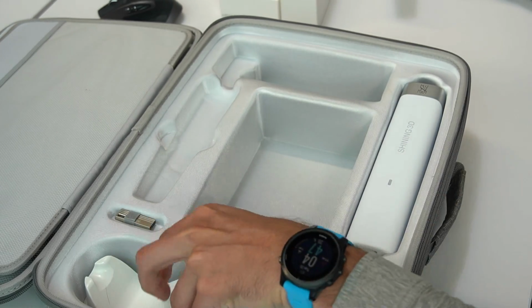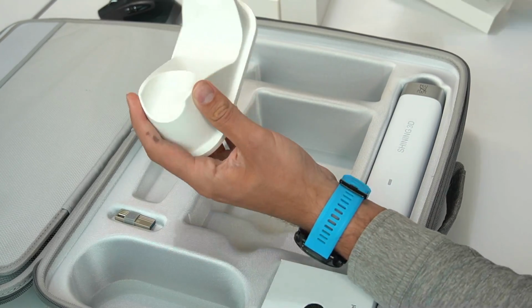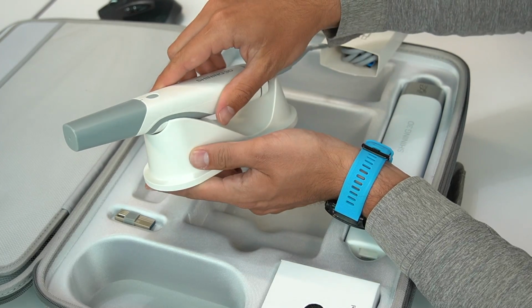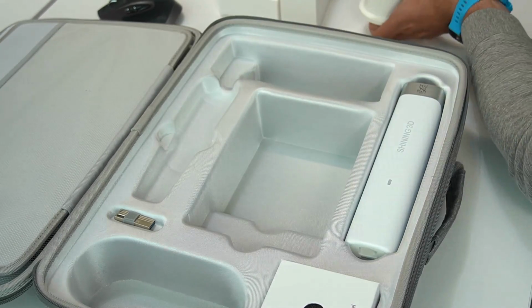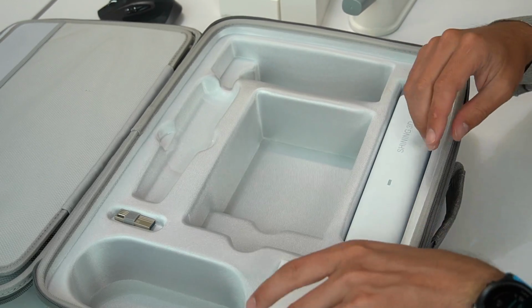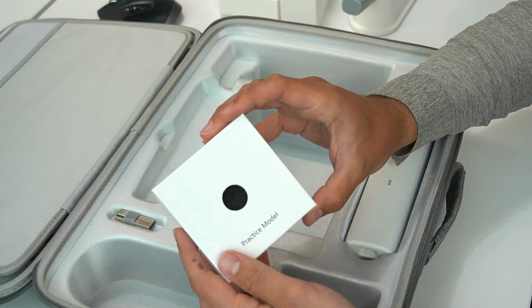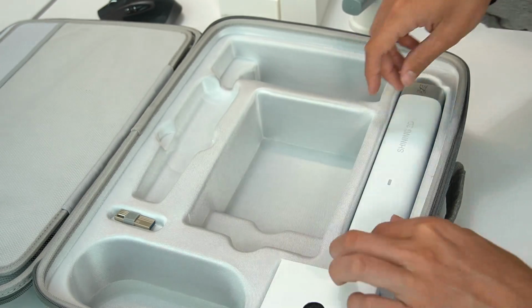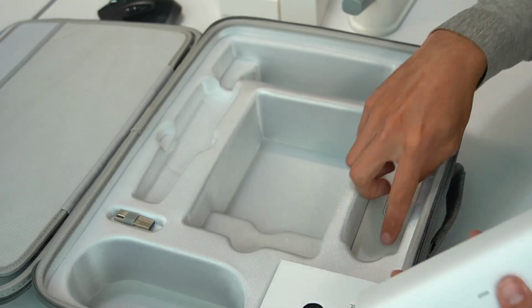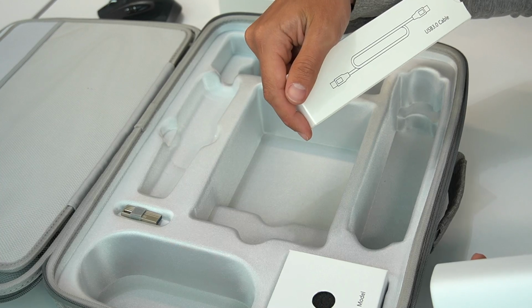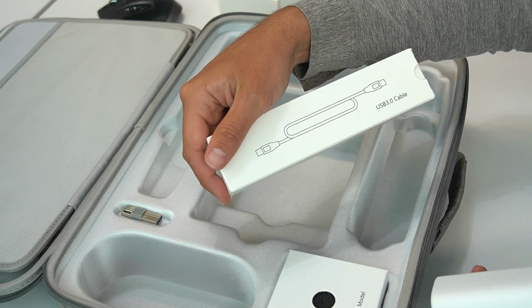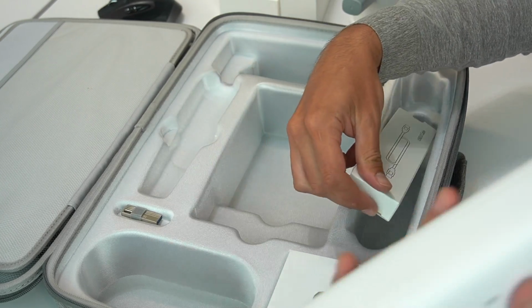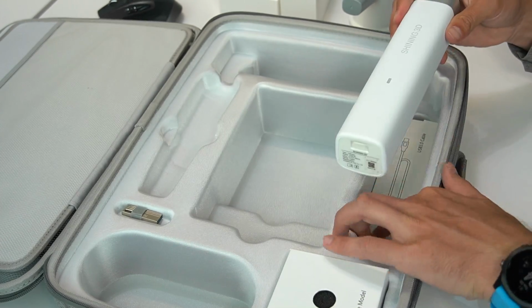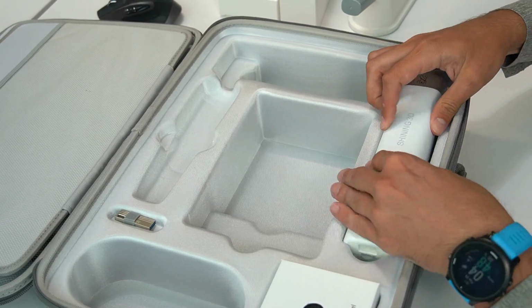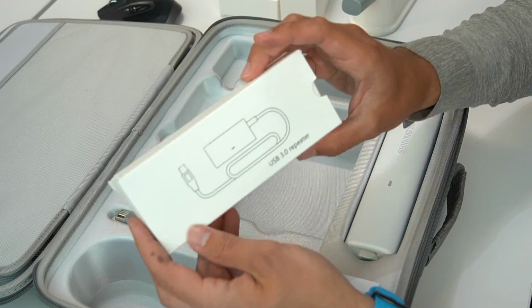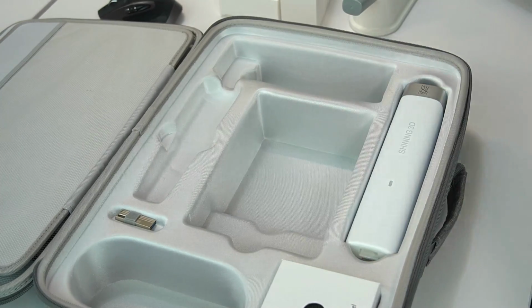I always like to keep my scanner in the cradle, so the scanner is held in the cradle like so. And then they give you a practice model to practice your scans on, which is quite convenient. A calibration tool and a calibration cable. This is why you need 2 USB outlets on the laptop: you're going to need to plug this into your laptop and then into the calibration tool, as well as the scanner itself into the repeater, and then your repeater is what plugs into your laptop.